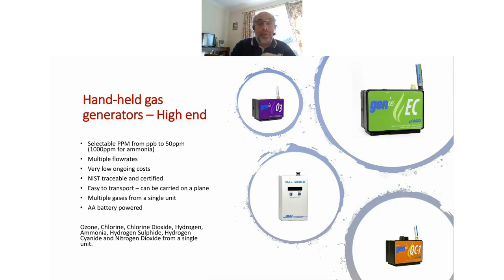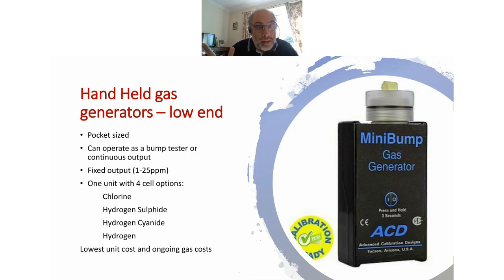So also to say, there is a low end of these generators. These are very small. These are pocket size. These fit into your trouser pocket if you want, or your shirt pocket. They typically operate as a bump tester, in that you'd get a small 90-second outflow of gas to bump test an instrument. They're not certified in the same way, therefore, but you will have a fixed output here.